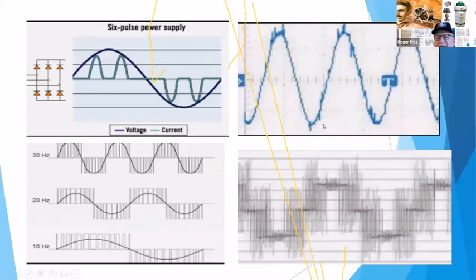And one of the factors that comes up is that as you go longer lead lengths coming out of the output of the drive to the motor, anywhere from 100 feet and above, these voltages will actually increase. So you'll see these spiking voltages here that are going above. That's what's causing some of the failures in submersible motor applications, because the voltage windings were designed maybe at 1200 volt wire, and sometimes we're seeing spikes of 1500 volts, 2000 volts the longer that you go, because you get that harmonic effect.